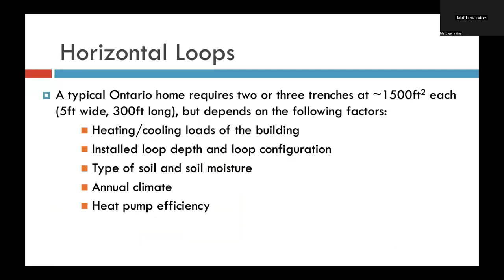So a typical Ontario home is going to require two or three trenches at approximately 1500 square feet each. Again, that's 5 feet wide, 300 feet long, but it would depend on the following factors: the heating and cooling loads of the building. That would be the heat loss, heat gain calculations that you would do for any building to determine, on the coldest day of the year, how many BTUs per hour you need, versus on the warmest day of the year, how many BTUs per hour you need to remove from the building. And then the installed loop depth and loop configuration, the type of soil and soil moisture, obviously the annual climate. And then of course the heat pump efficiency also has an impact on loop design. Next, please.